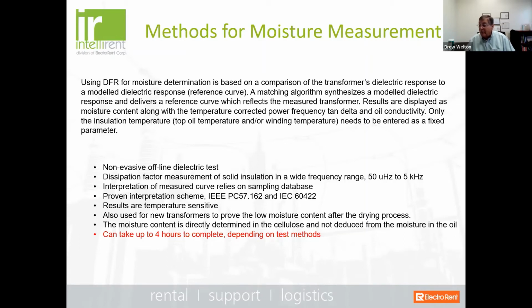The dissipation measurement of solid insulation is what you're looking at. This is disregarding what's in the oil. This is what's in the insulation, and that's where our big concern is. The interpretation of the measured curve relies on the sampling database that was built into the software that actually gives you your measured results. And this is a proven interpretation scheme. This is all part of IEEE PC57.162 and IEC standards 60422. The results are temperature sensitive, so it is important to record your temperature at that time. And they actually use this under drying conditions for brand new transformers. A lot of the factories have taken this method to make sure that you're getting delivery of dry insulation.